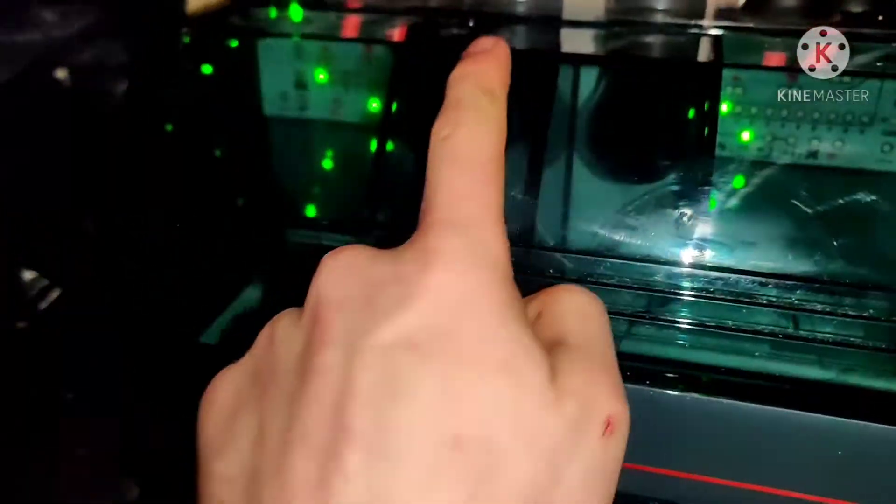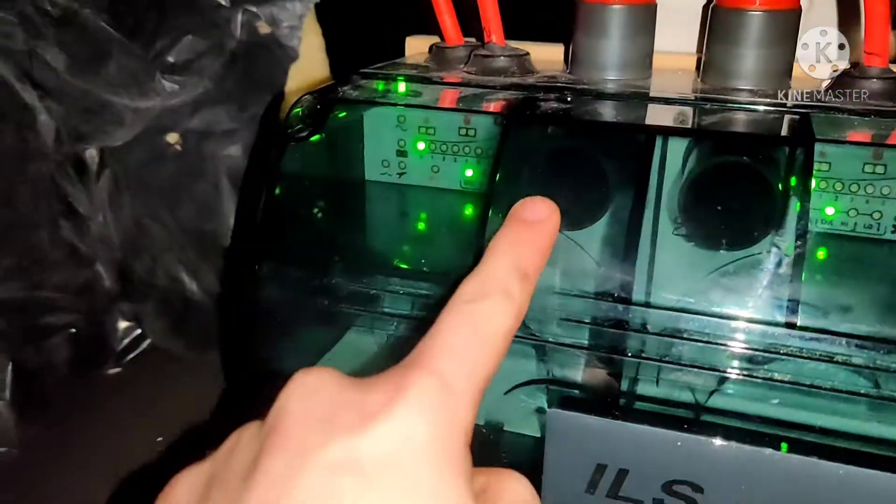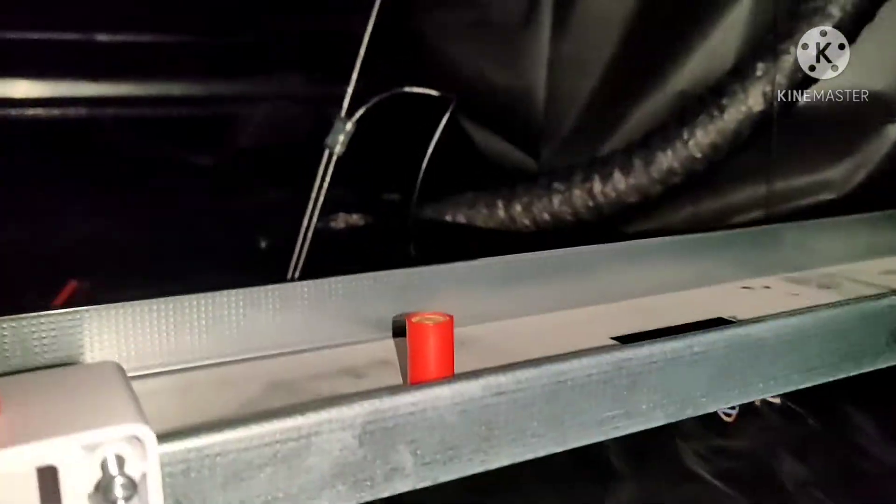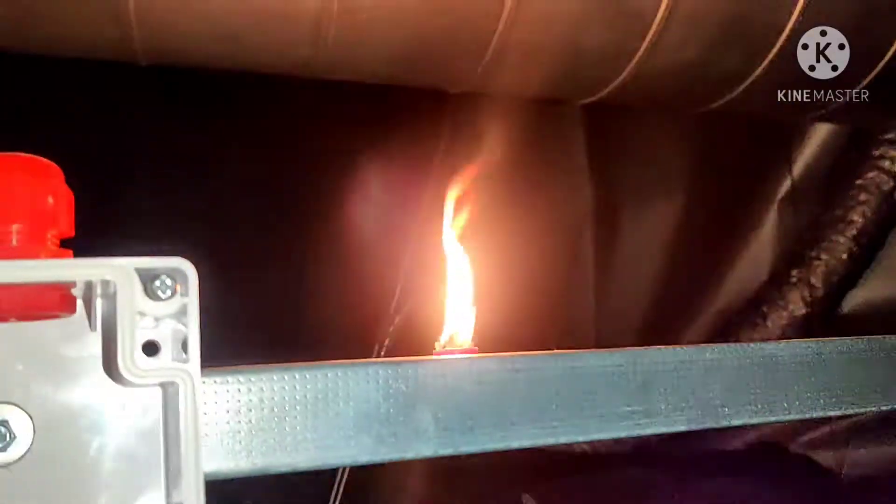The air is coming from holes in all of these pipes at the top of the roof space. If there's smoke, it pulls the air and smoke through the pipes into that detector and sets the fire alarm off. There's a little exhaust pipe at the bottom there as well. I've got a smoke pellet here and I'm just going to light that.